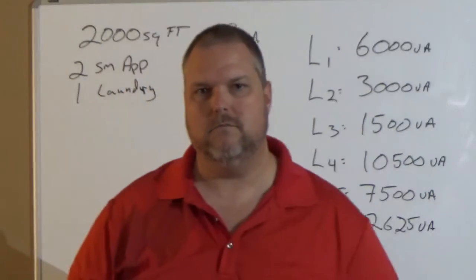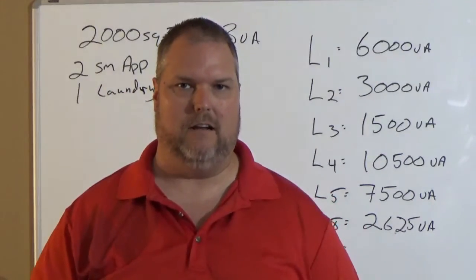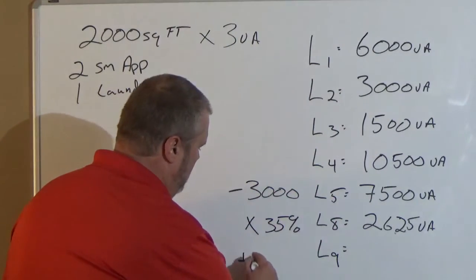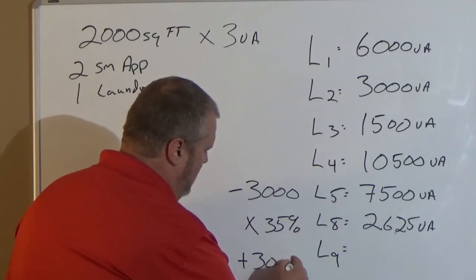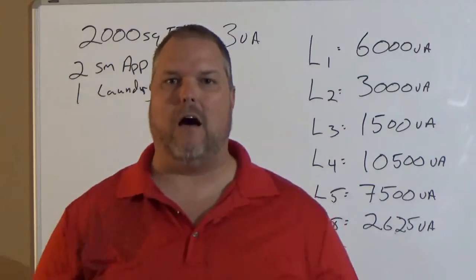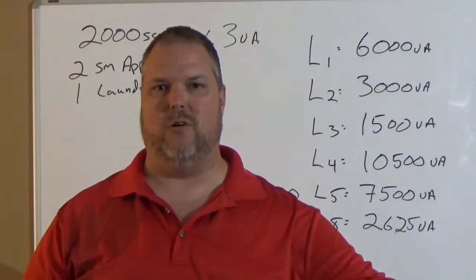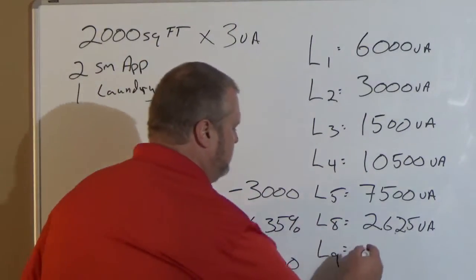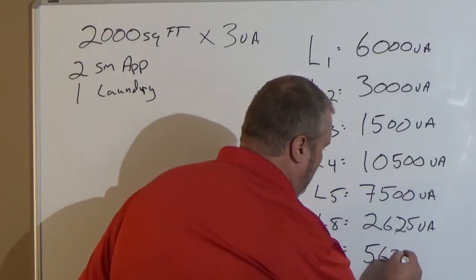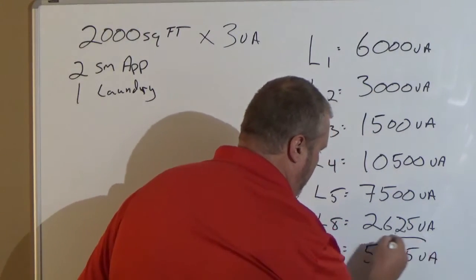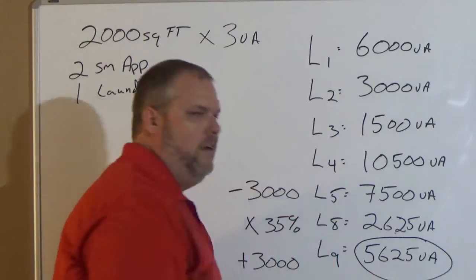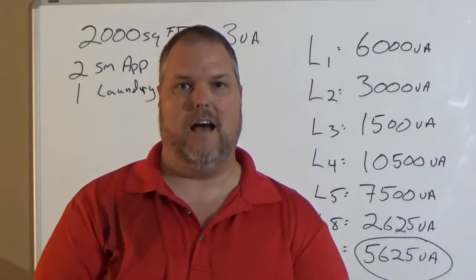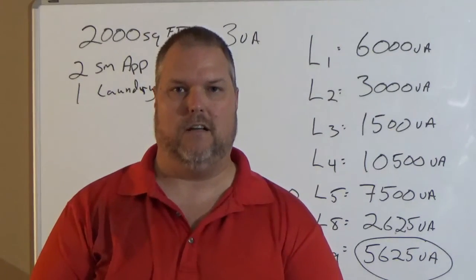Are we done yet? No. Because now we have to fill in line 9. Line 9, what we're going to do is add 3,000 back into it. So now I'm going to take that 2,625, I'm going to add 3,000 back into it and it's going to give me 5,625 and that is in line 9. Line 9 is my general lighting load.